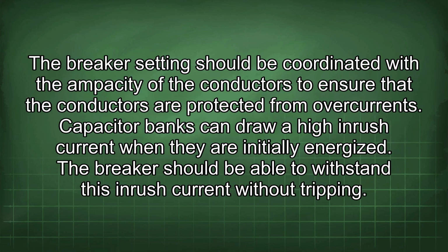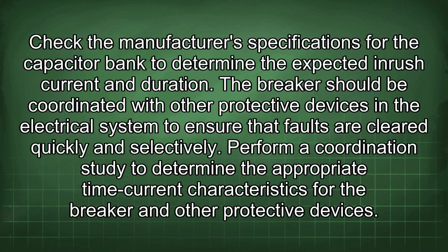The breaker setting should be coordinated with the ampacity of the conductors to ensure that the conductors are protected from overcurrent. Capacitor banks can draw a high inrush current when they are initially energized. The breaker should be able to withstand this inrush current without tripping. Check the manufacturer's specifications for the capacitor bank to determine the expected inrush current and duration. The breaker should be coordinated with other protective devices in the electrical system to ensure that faults are cleared quickly and selectively. Perform a coordination study to determine the appropriate time current characteristics for the breaker and other protective devices.